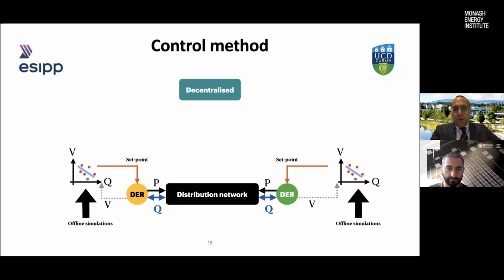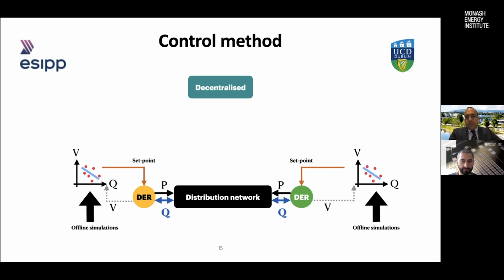If something changes in the grid, we have to update those curves. But when we say something changes, it doesn't mean the loading of the system, because those loadings are already considered in the offline simulation phase. If something big happens in the system—for example, part of the network gets disconnected from the rest, and the network topology changes—then we should send signals to do the update, or update the volt-var curve manually somehow.